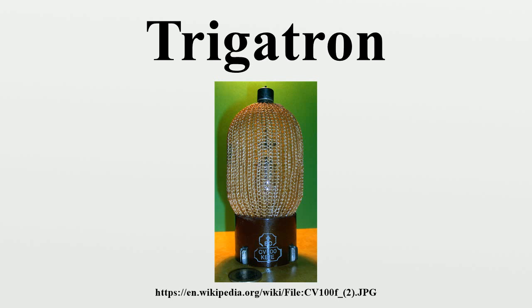The triggering electrode is most often mounted through a hole in the center of the positive main electrode. The undrilled main electrode is the negative electrode. When switching high currents, the electrodes undergo considerable heat stress, as they are directly involved in the electric arc. This causes the surfaces to undergo gradual vaporization. So some designs incorporate methods to easily adjust the distance between the electrodes or to actually replace the electrodes. The main electrodes are typically fabricated from brass or alloys of copper and tungsten for longer electrode life.